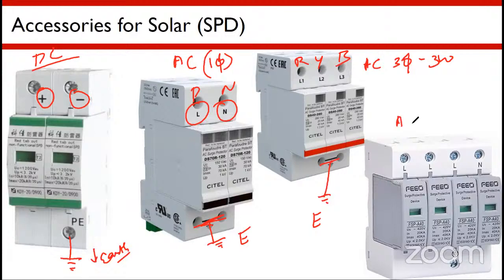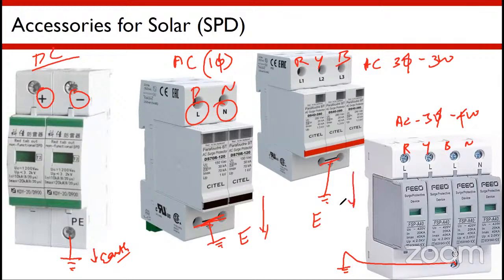Here what you are seeing is the AC three-phase, four-wire system, which includes L, L, L, N, nothing but R, Y, B and neutral, but the output is common. So irrespective of whether the fault happens in positive, or positive and negative together, or in phase, or neutral, or phase and neutral shorted together, the fault will be diverted to the earth. That is the main objective of having this SPD here.